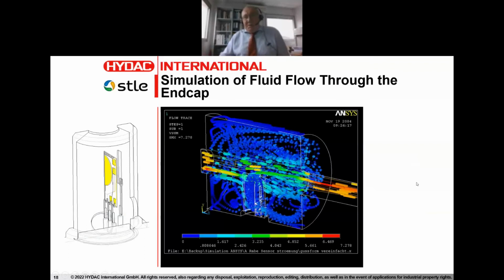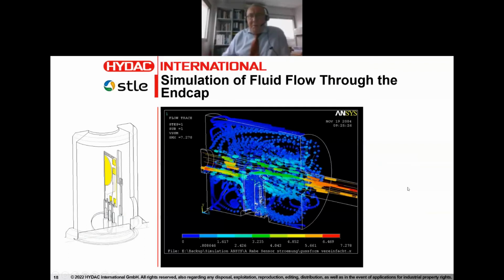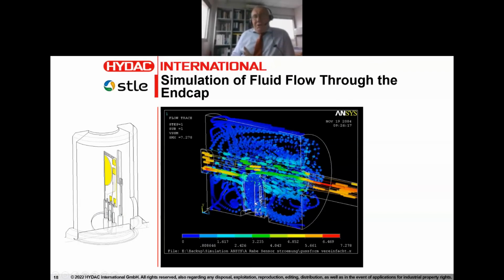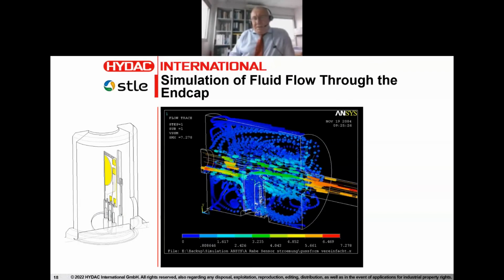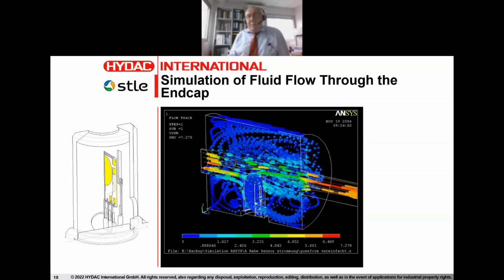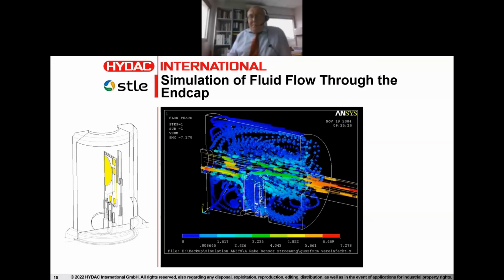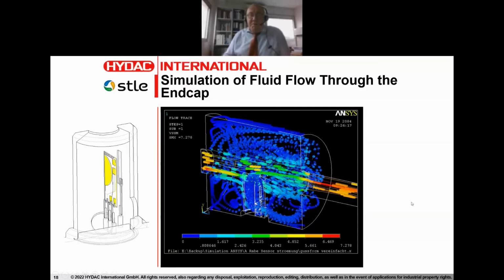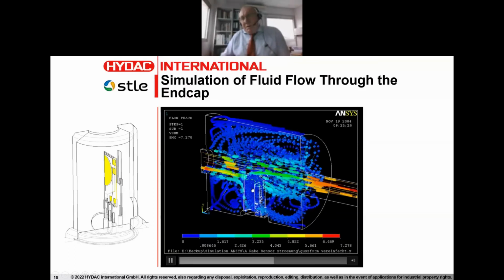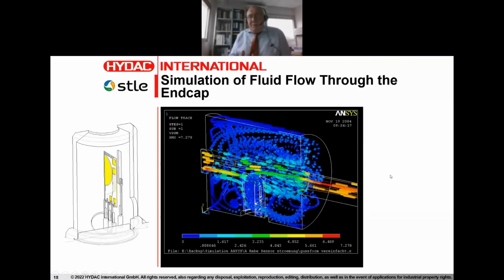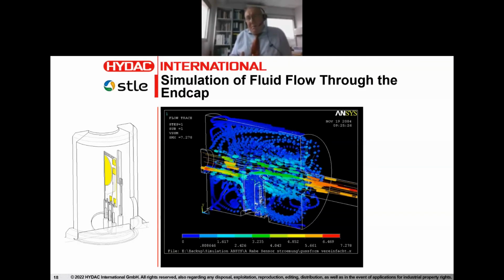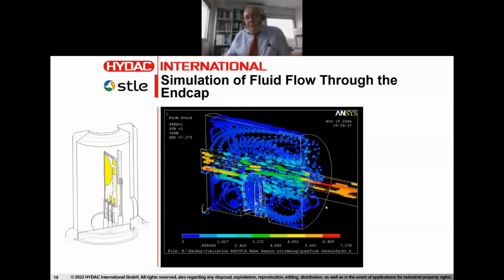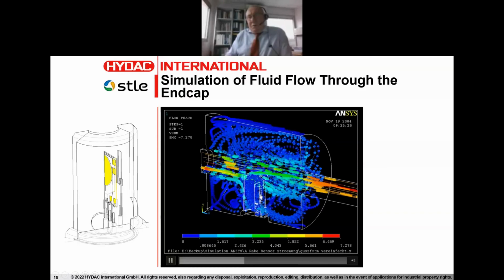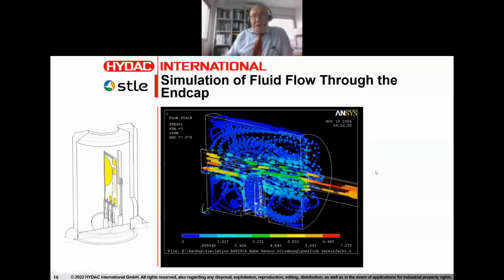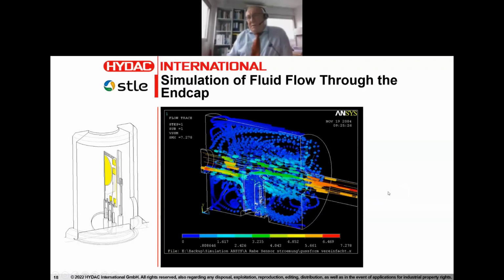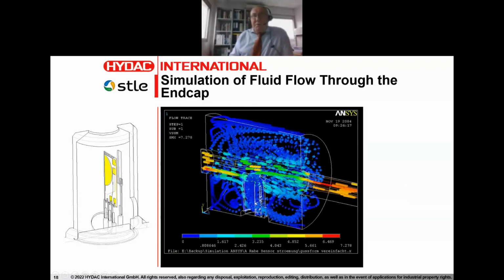In order for deposits not to form on the quartz crystal microbalance, it was necessary to make sure that this crystal is subject to constant scrubbing by the fluid flow. So we constructed computational fluid dynamic models and made sure that the surface of the crystal is constantly being scrubbed by the shear force, and that the crystal had to be mounted in an upside down configuration in order to facilitate the flow of the fluid through the system components.